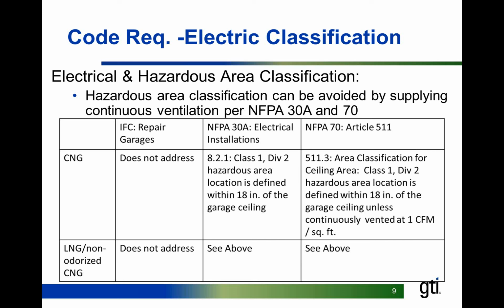A note here is that hazardous area classification can be avoided by supplying continuous ventilation, and that's in NFPA 30A and NFPA 70, the National Electric Code.